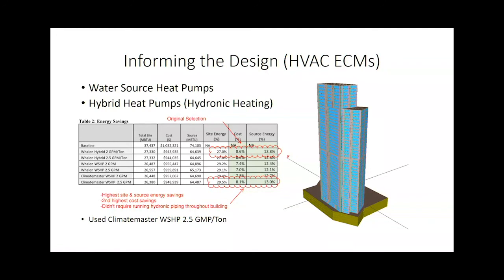So a hybrid water source heat pump works such that the cooling is done by the heat pump, but the heating is just done with a hydronic hot water coil in the terminal unit, which is connected to a base building boiler.